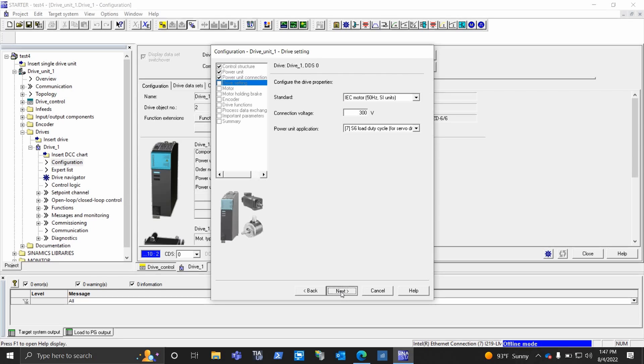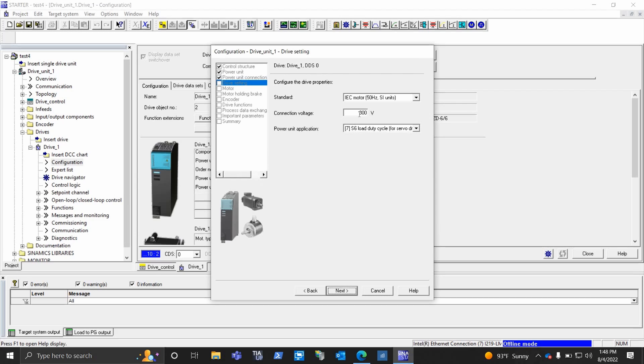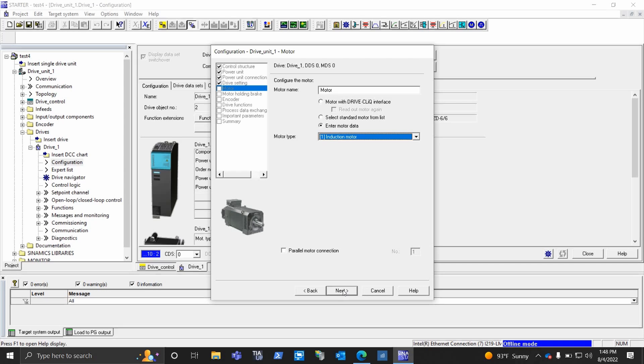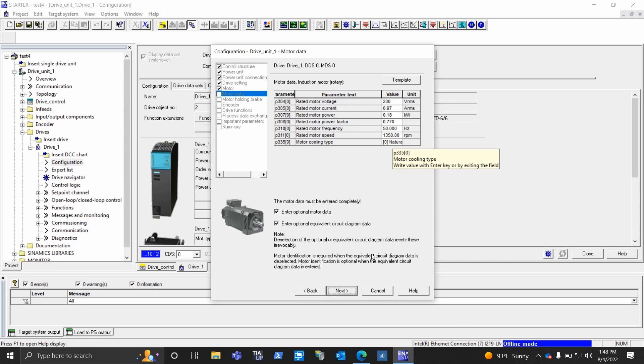These are settings that have been set previously and they stay unless you change them. Now this is a special demo, it's actually a 300 volt setup, which is kind of custom, so it's a little irritated at me about that. So it's going to make you change it here, and then behind the scenes I'll have to change it back, but I'll show you how it would look as a standard. I have just a regular old induction motor, and I'm just going to put in the data. If you select standard motor from list, that's for Siemens motors where you can put the part number in, but I don't have a Siemens motor for this example, just a generic motor. There's data that I've already put in. Again, everything stays unless you change it, so that's off the nameplate.